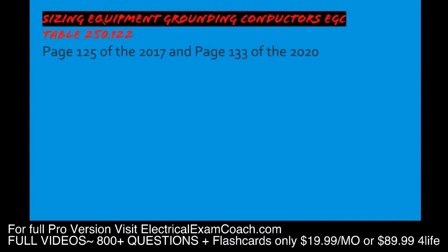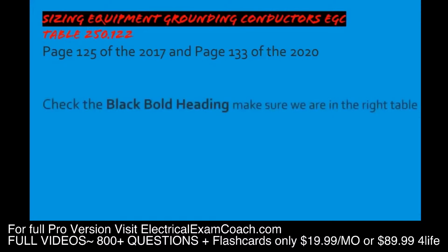And for that, we're going to use Table 250.122. It's on page 125 of the 2017 and on page 133 of the 2020. And I love this table because it's so easy to use. There's not all these crazy exceptions. It's very simple. So when we get there, the first thing that we do is we read the black bold heading to make sure we're in the right table. Minimum size equipment grounding conductors. Great, I feel like we're in the right table.